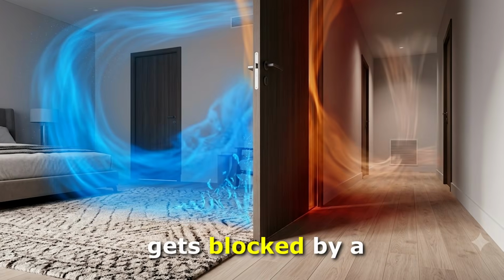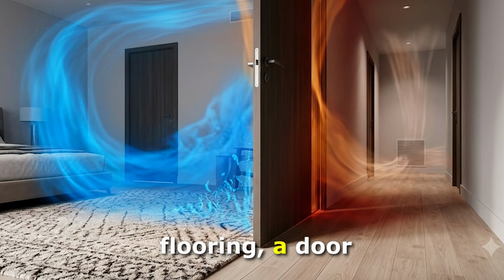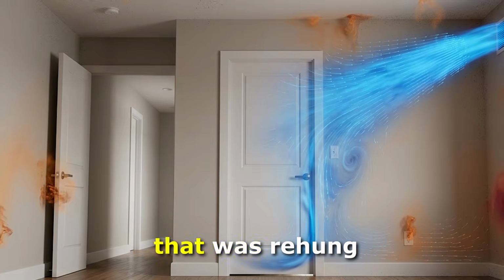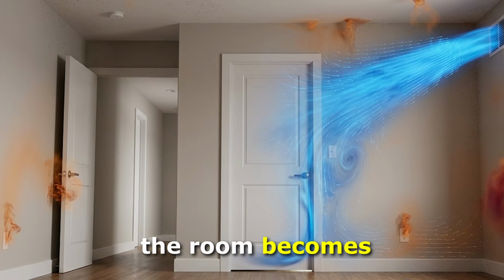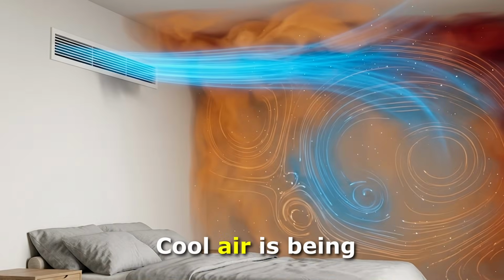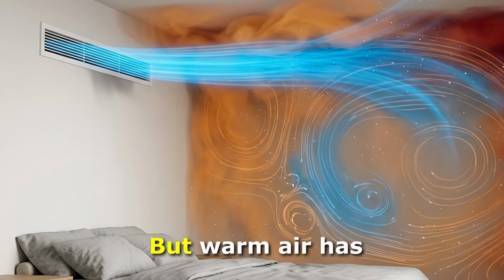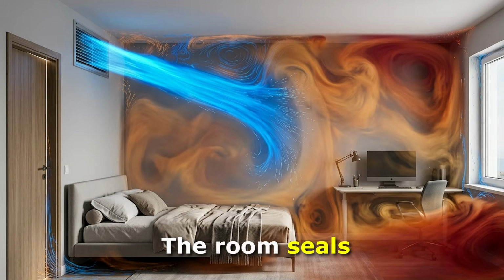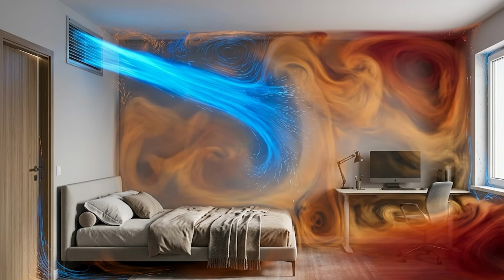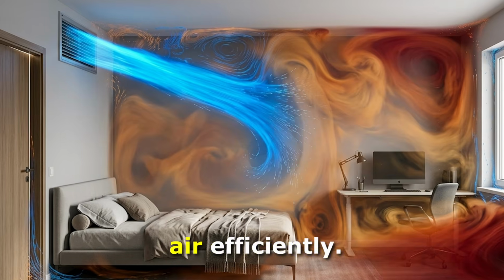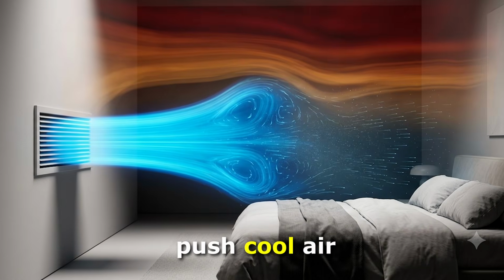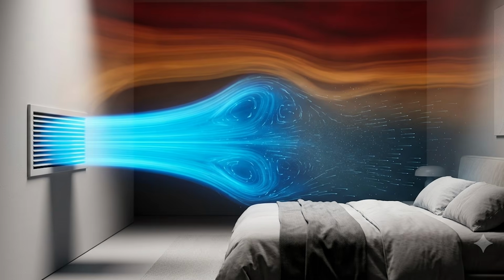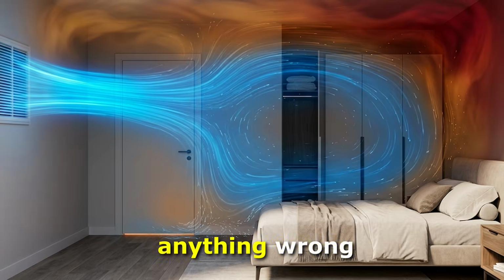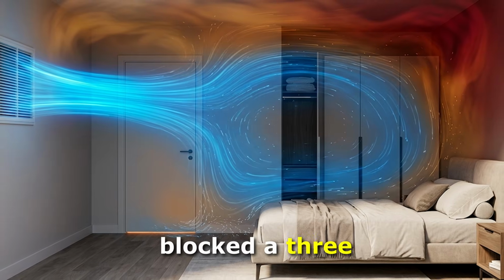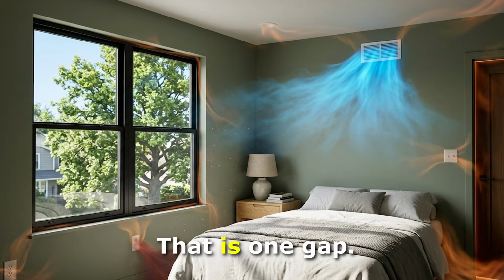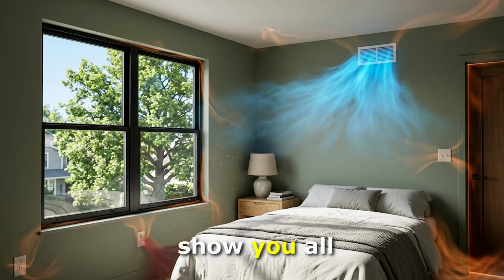But if that gap gets blocked by a thick rug, new flooring, a door sweep someone added for noise, a door that was rehung slightly too low, the room becomes pressurized. Cool air is being pushed in through the supply vent, but warm air has nowhere to go. The room seals itself, and once it pressurizes, the supply vent essentially stops delivering air efficiently. You are trying to push cool air into a balloon that is already full. The room gets hotter. Not because of anything wrong with your AC, because you blocked a 3/4 inch gap under a door. That is one gap, and I am about to show you all the others.